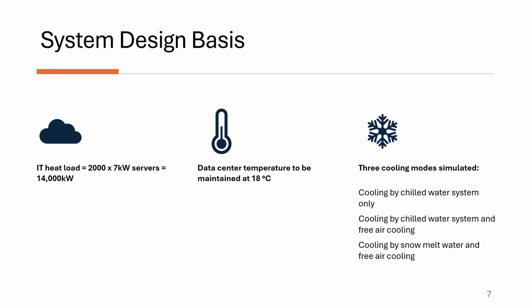The data center for our simulation generates 14,000 kilowatts of heat from the IT equipment. This is comprised of 2,000 x 7kW servers. The space is to be maintained at a temperature of 18 degrees Celsius. Three cooling modes were simulated. The first was cooling by the chilled water system only. The second was cooling by the chilled water system and free air cooling. And the third was cooling by snow melt water and free air cooling.